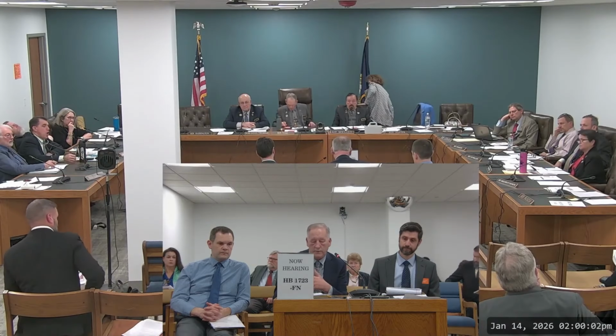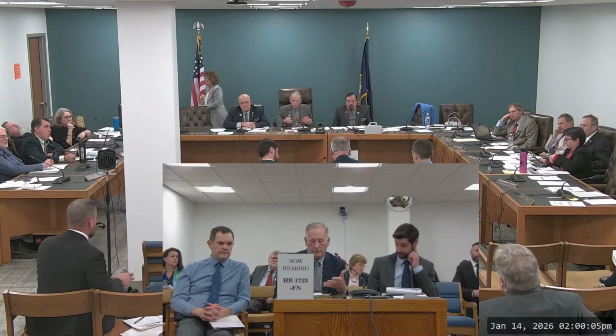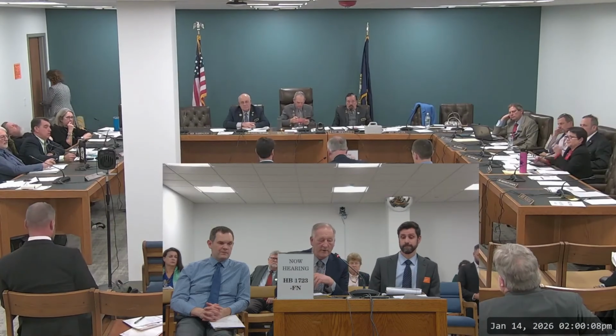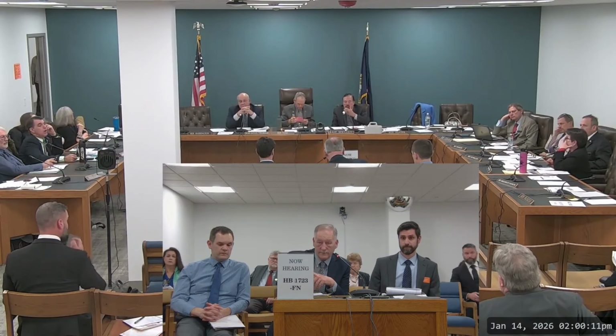So we do get notice pretty far in advance of when a magnetic storm is about to approach. We have system operators 24/7 looking at the system. They are watching VAR flow—VAR flow is a component of power where current is flowing. I don't want to get too deep into it, but we do get indication on the system if there is excessive current and excessive reactive VAR flow. So the operators could take action. You wouldn't kill everything, you'd kill or de-energize a piece of equipment so that it wouldn't get damaged.